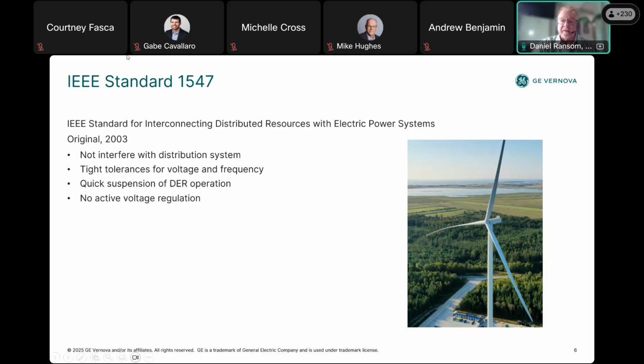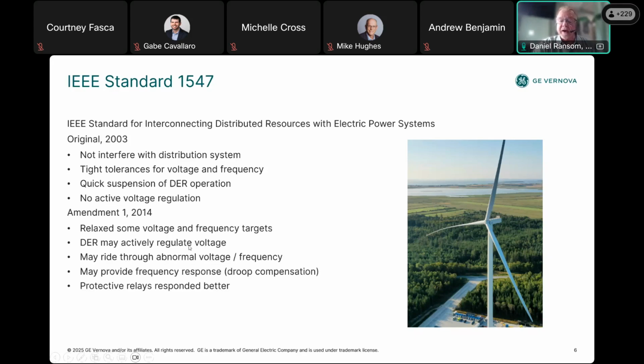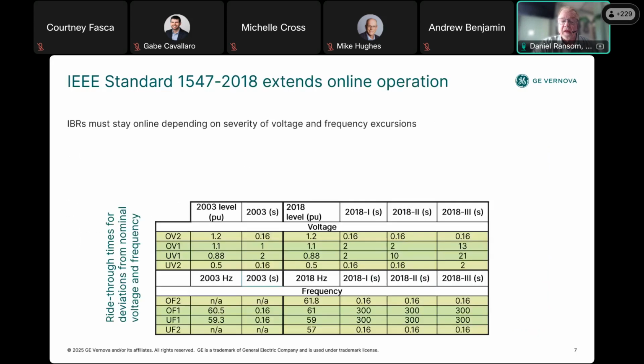Well, that changed. Because of the increased adoption of DERs in the power grid, Amendment 1 came about in 2014. It relaxed some of the voltage and frequency targets. Now the DER may actively regulate voltage and may ride through abnormal voltage and frequency and may provide frequency response. This helped with grid support that is needed for adequate protection schemes, keeping the relays so that they have quantities on which to operate. So what the standard said is that IBRs must stay online depending on the severity of voltage and frequency excursions.